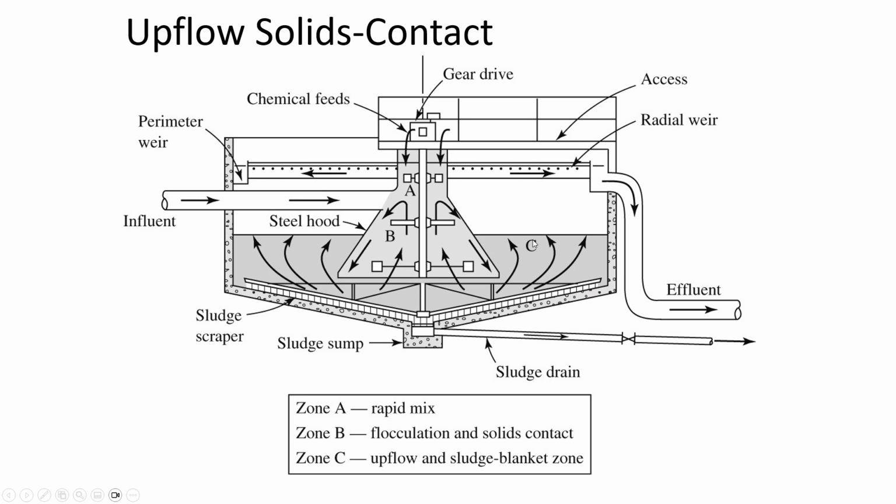So as the diameter is increasing, that's also a chance for the gradual reduction in mixing energy that we associate with what's happening in flocculation. Remember that we want the flock to get gradually larger, and so having the diameter increase is increasing the cross-sectional area, and it would therefore be reducing the flow rate. And you can see that if you've got an increasing cross-sectional area, but the central shaft is rotating at the same speed, that's just a way of reducing the mixing energy. And so the G value, the velocity gradient, would be going down.